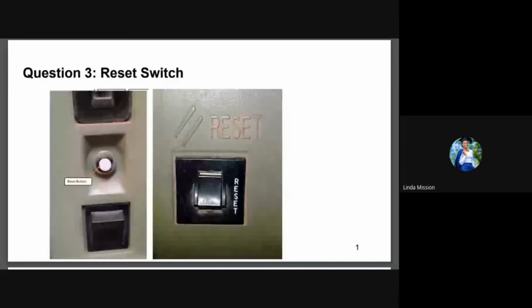Thank you, Maui. Every oxygen concentrator has a circuit breaker, which is labeled as a reset button on its front panel. And the main function of the reset button is to protect the electrical circuits from overload. Thus, when any component inside the concentrator, for example the compressor, is drawing more electrical current than it is supposed to, the reset button trips to automatically switch off the concentrator. In some circumstances, the reset button may trip due to poor mains power or when the button itself is faulty.